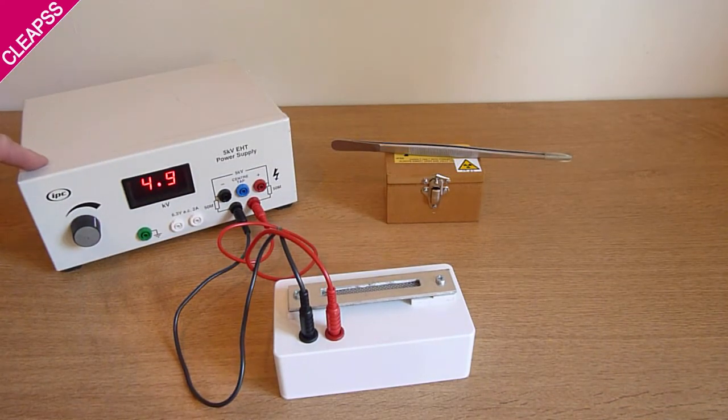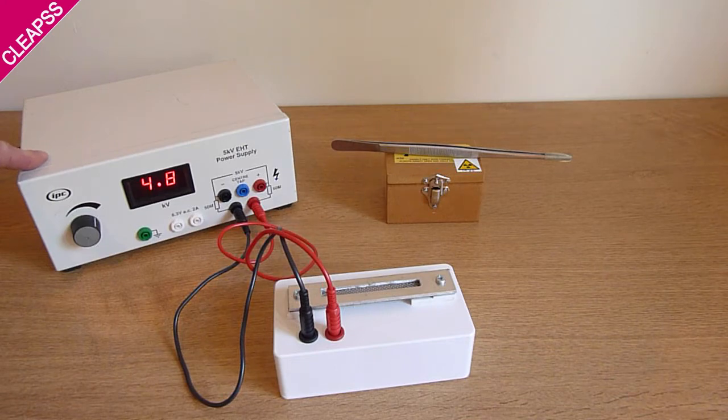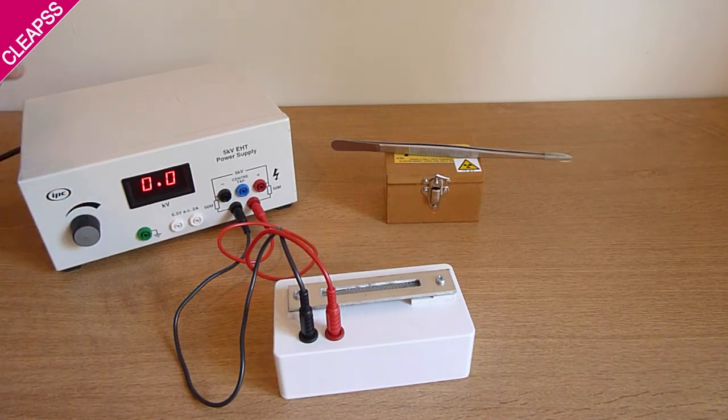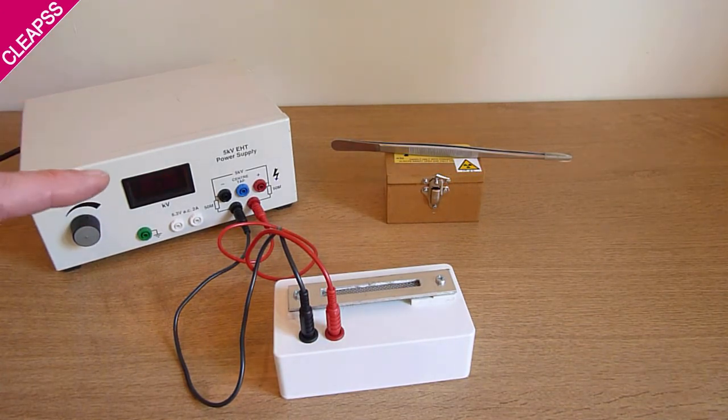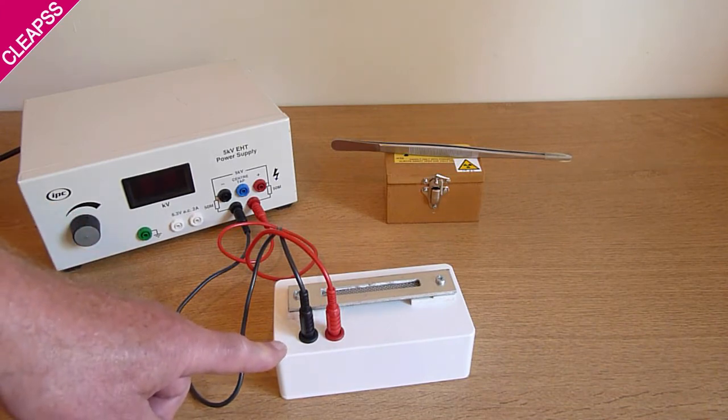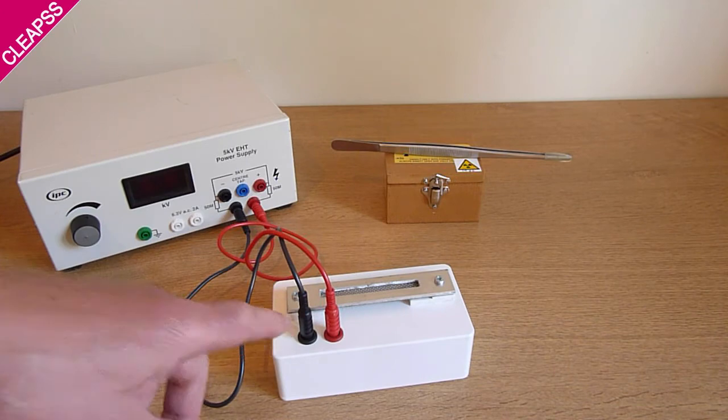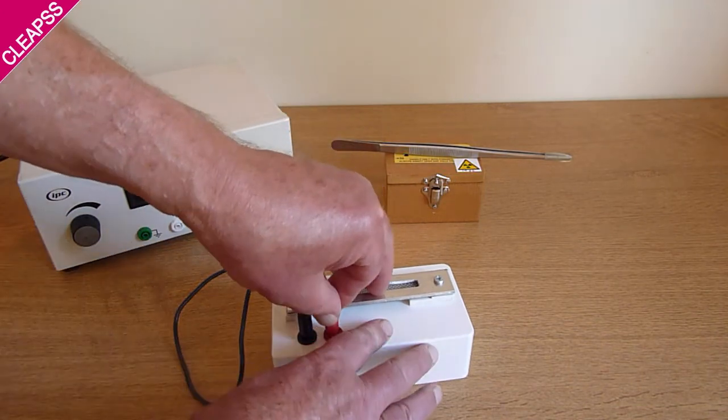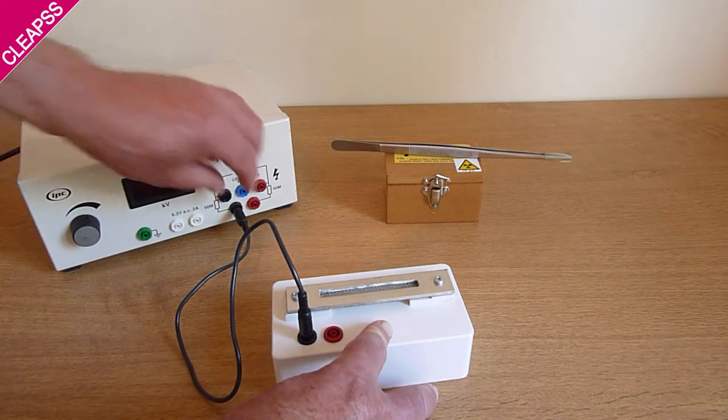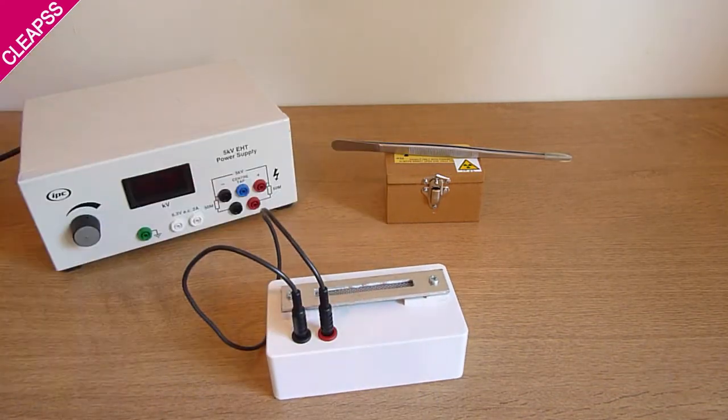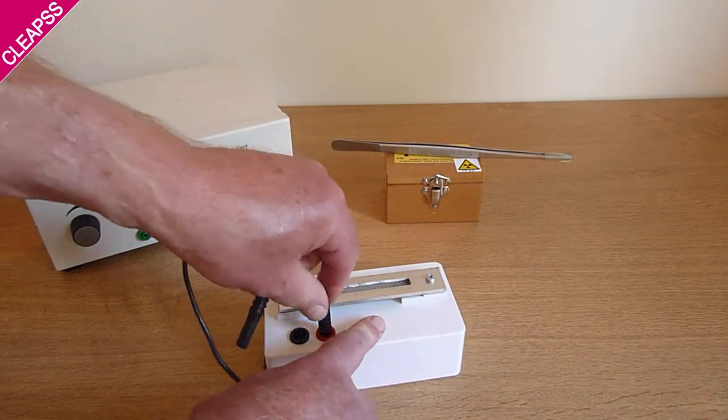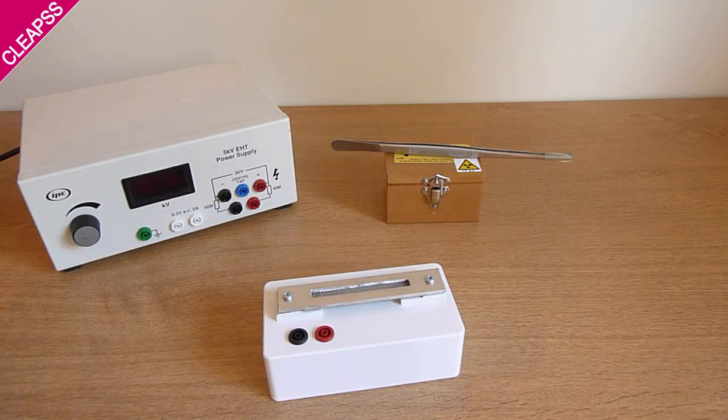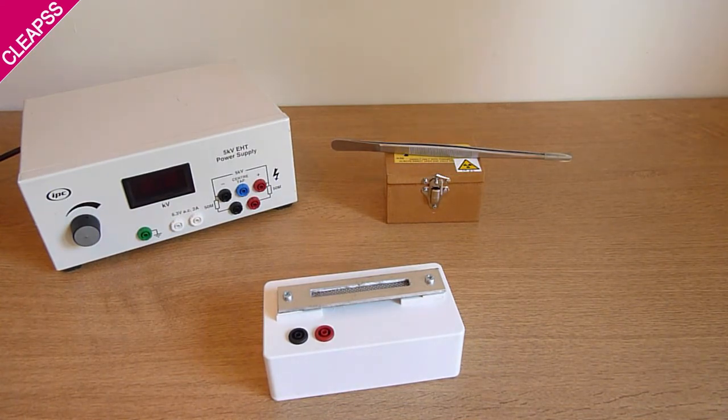Now the EHT unit, this is an IPC, same as the Griffin one, must be current limited to less than 5 milliamps. So if you were to touch the contacts accidentally, it'd be a very unpleasant shock, but no more than that. I've finished. I'll just turn the voltage down to zero and turn it off. One thing to be careful here - there's a capacitor inside the spark counter. If you accidentally touch the contacts, you can get a very unpleasant shock. So I will just short out the contacts and that stops that from happening. And that shows me handling a standard cup sealed source.